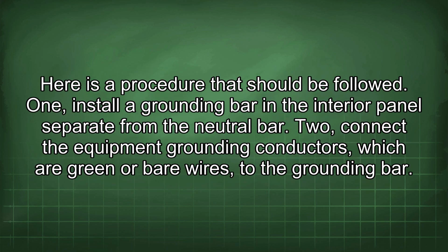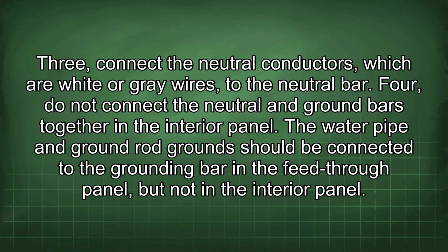Here is a procedure that should be followed. 1. Install a grounding bar in the interior panel separate from the neutral bar. 2. Connect the equipment grounding conductors, which are green or bare wires, to the grounding bar. 3. Connect the neutral conductors, which are white or grey wires, to the neutral bar. 4. Do not connect the neutral and ground bars together in the interior panel.